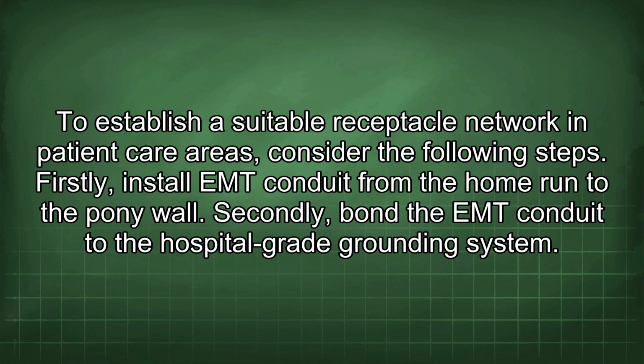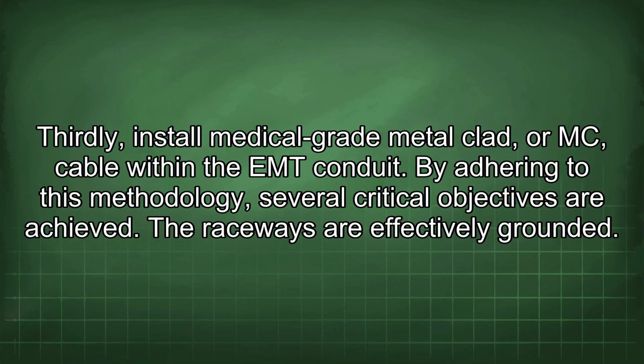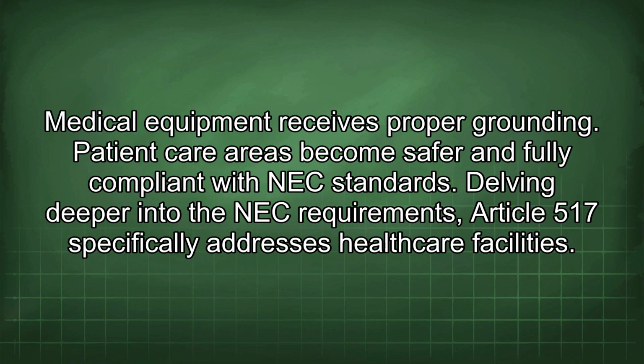To establish a suitable receptacle network in patient care areas, consider the following steps. Firstly, install EMT conduit from the home run to the pony wall. Secondly, bond the EMT conduit to the hospital-grade grounding system. Thirdly, install medical-grade metal-clad, or MC, cable within the EMT conduit. By adhering to this methodology, several critical objectives are achieved. The raceways are effectively grounded. Medical equipment receives proper grounding. Patient care areas become safer and fully compliant with NEC standards.